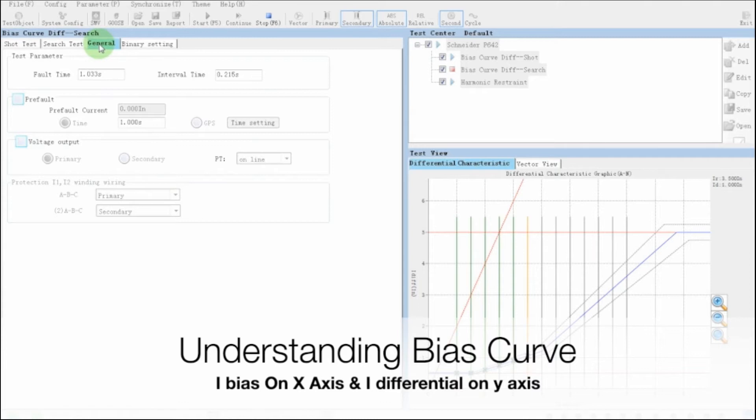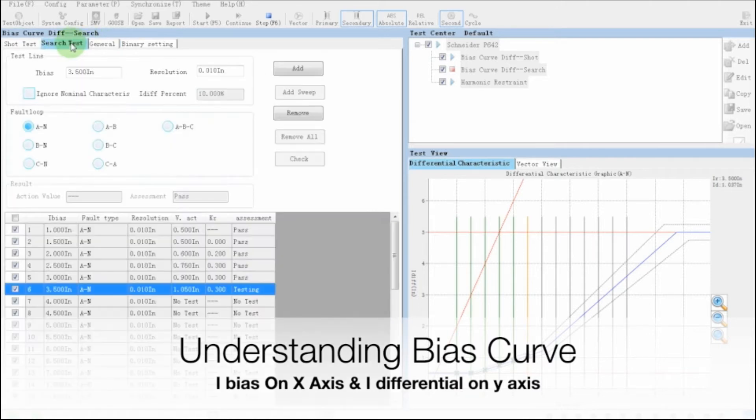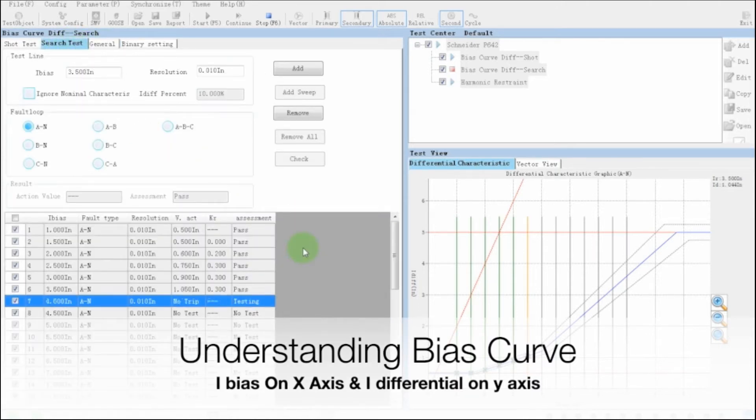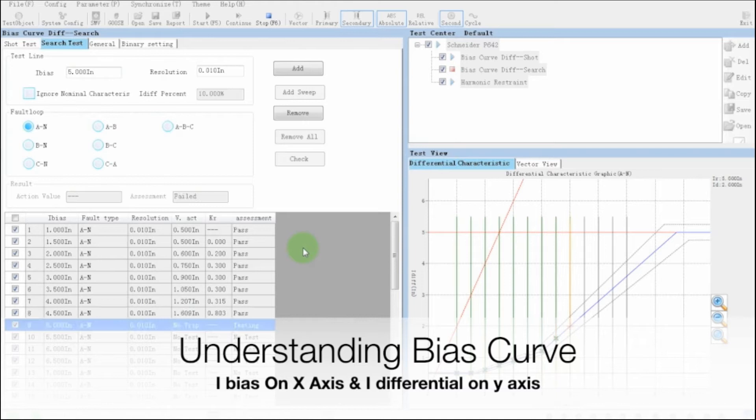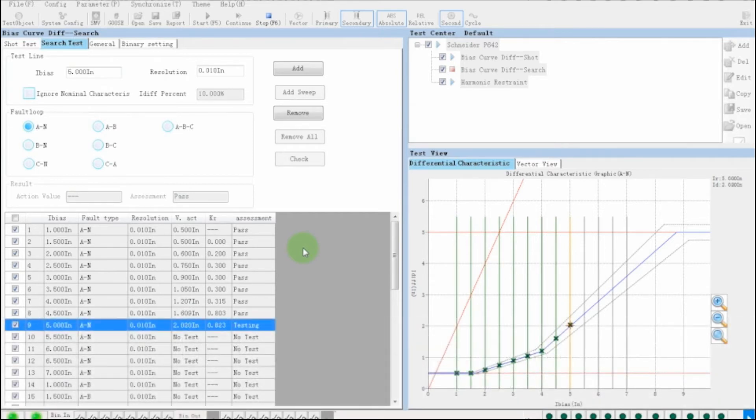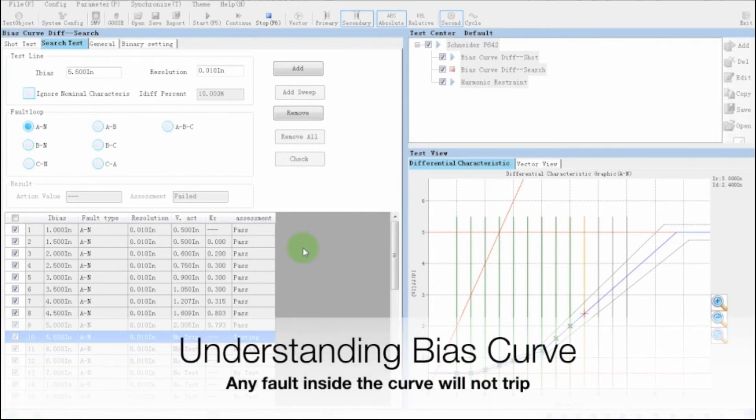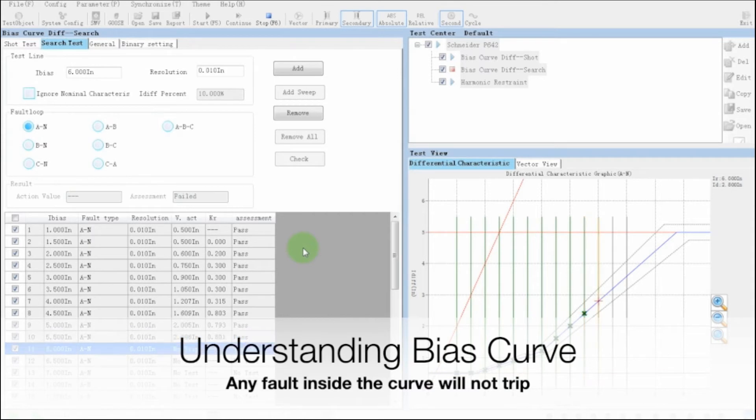Whenever we are testing a bias curve, we have i-bias on x-axis and we have i-differential on y-axis. The blue line is the curve correctly set in the relay. Any faults which is under this bias curve will not trip.